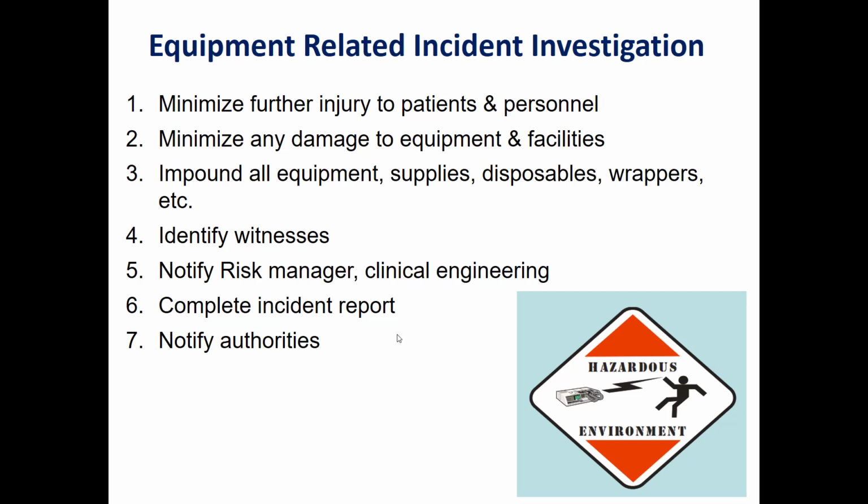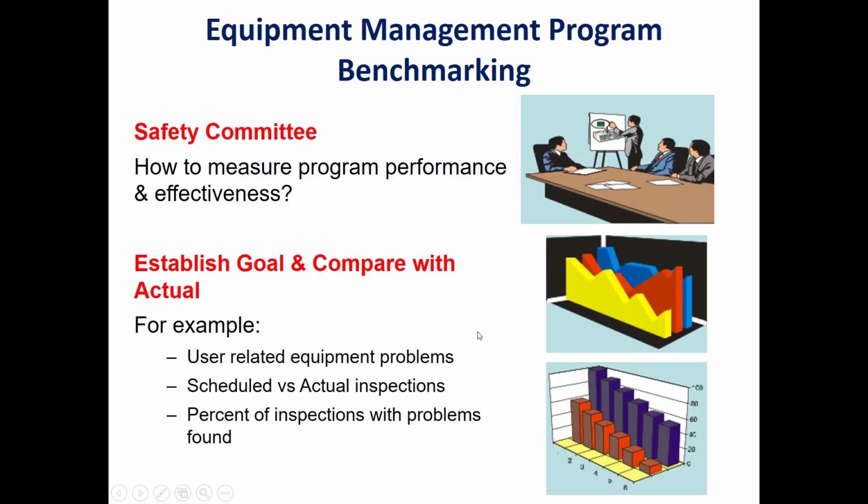What we mean by the authorities, for example, is the FDA in the US. We should send a notification in case a major injury or harm has been caused to the patient or the staff due to the use of this medical equipment.